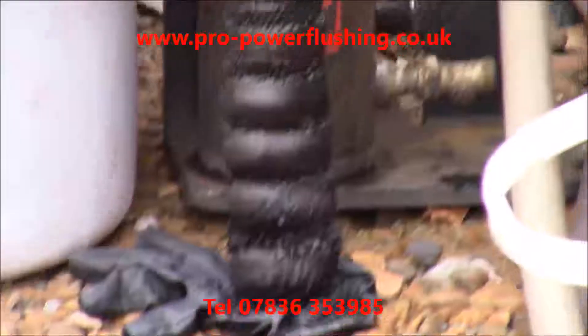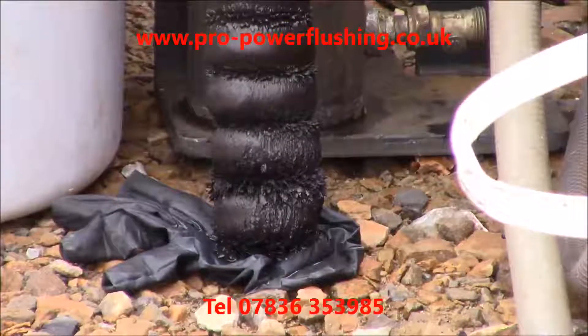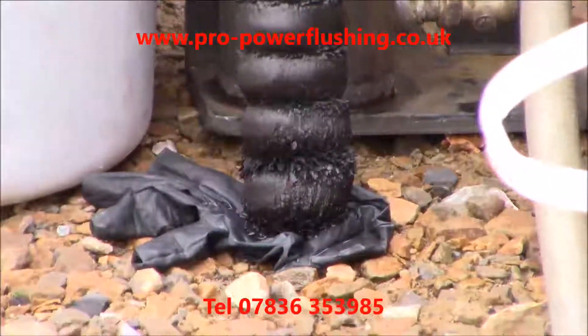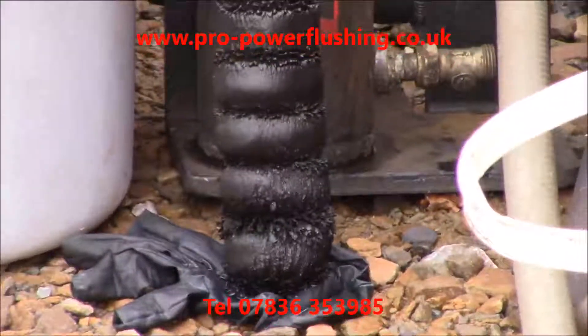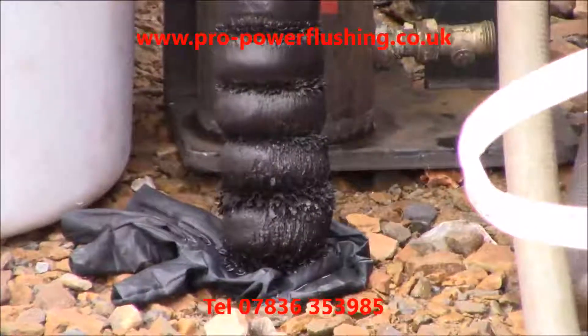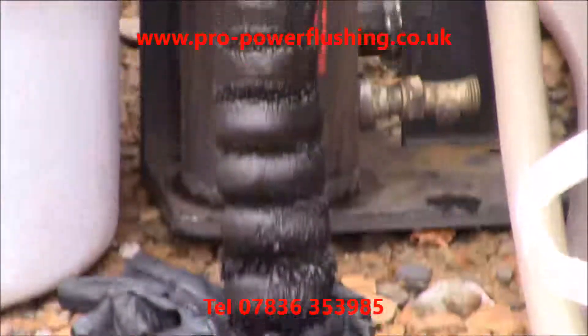Imagine fitting a new boiler and all this rust and corrosion going through the system. We've been to many central heating boilers that have just broken down within the first month because the system wasn't power flushed. Engineers and boiler fitters come round and fit a boiler without power flushing the system, and all this rust and corrosion gets into the boiler and blocks it up. It can actually write your boiler off — if this gets into the heat exchanger, it bakes on because there's no flow and the boiler's getting hot. It's of the utmost importance that you get your central heating system power flushed. Even new systems break down if not cleaned to BS 7593 standard. If they're not power flushed, you're just asking for trouble.